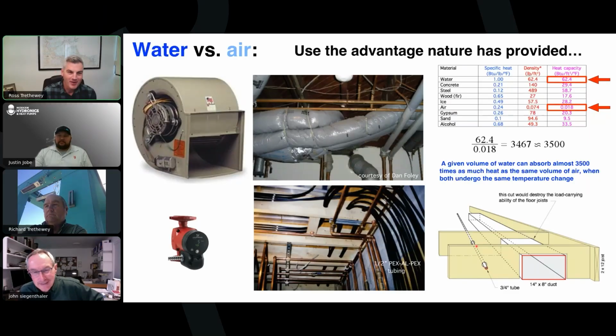Well, maybe a surprise to you, or maybe not - I probably would do something similar to what my dad just mentioned, an air to water paired up with hydronic radiant. But I'd say if budget wasn't an issue, I would actually go geothermal, water to water. If I truly had no budget constraints, I would go with a hydronic-based system but try to remove the outdoor equipment altogether and just do a vertical closed loop borehole system, going water to water, using hydronics in the building for my heating and cooling - the same kind of terminal distribution equipment we're talking about, with radiant and hydro air for sure would be the way I'd go. But obviously I have a limited budget, so I would go air to water because I think that's a far more effective strategy than drilling, et cetera.